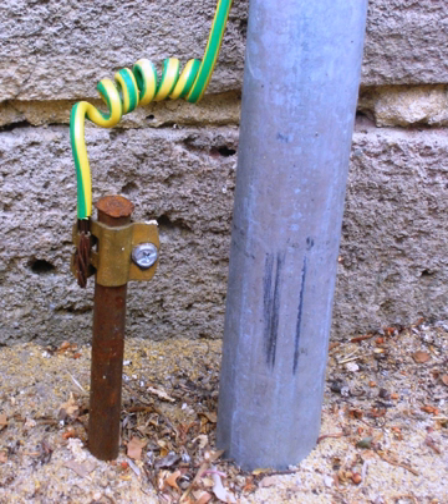Some high-voltage direct current (HVDC) power transmission systems use the ground as second conductor. This is especially common in schemes with submarine cables, as sea water is a good conductor. Buried grounding electrodes are used to make the connection to the earth. The site of these electrodes must be chosen carefully to prevent electrochemical corrosion on underground structures.